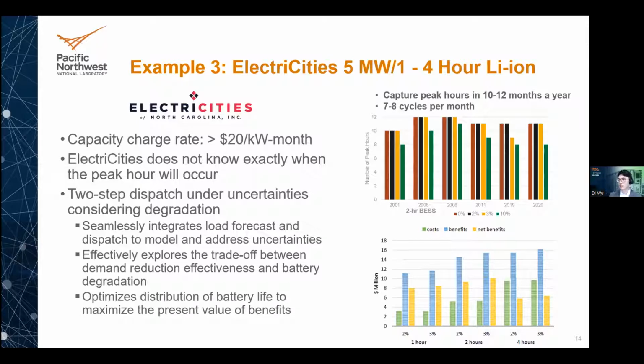The technical challenge is that Electricities and their member utilities don't know exactly when the peak hour will occur. Discharging the battery during all high load hours will speed up degradation, and there is also a risk of missing the system peak hours. So advanced control, valuation, and sizing methods are required to better address the operational uncertainties considering battery degradation effects. We developed a 2-step dispatch and evaluation framework that seamlessly integrates load forecasting and charging control.